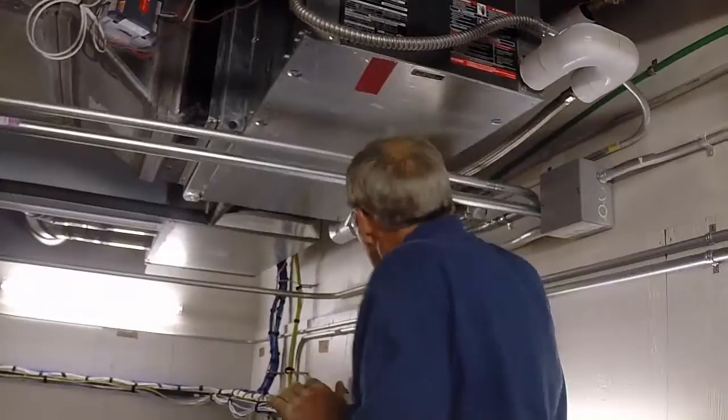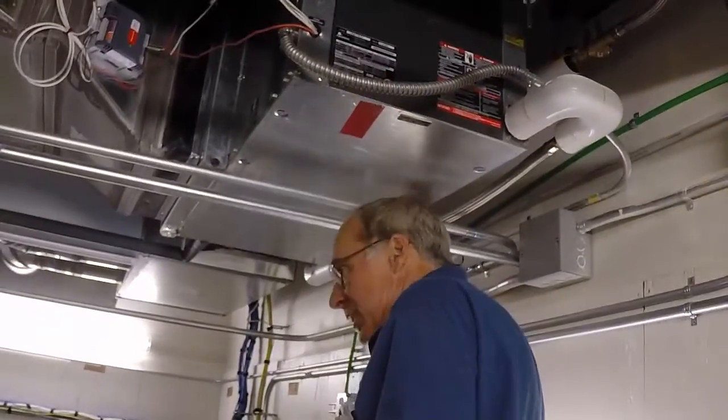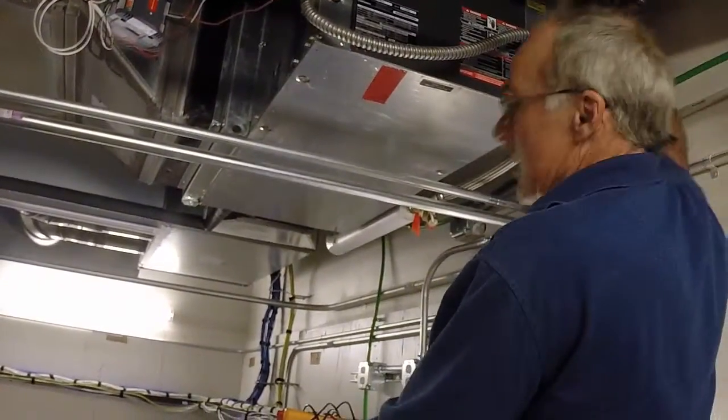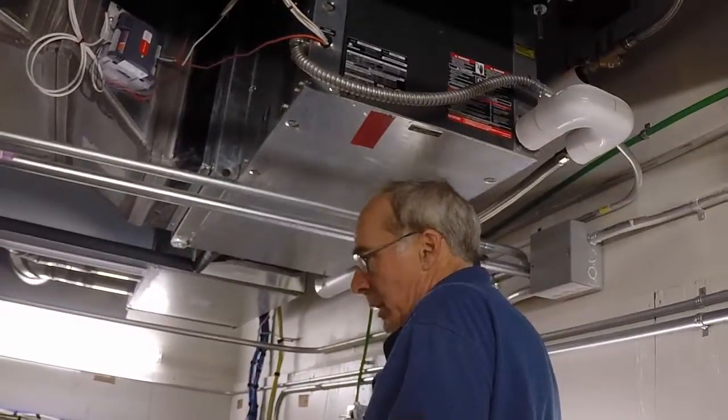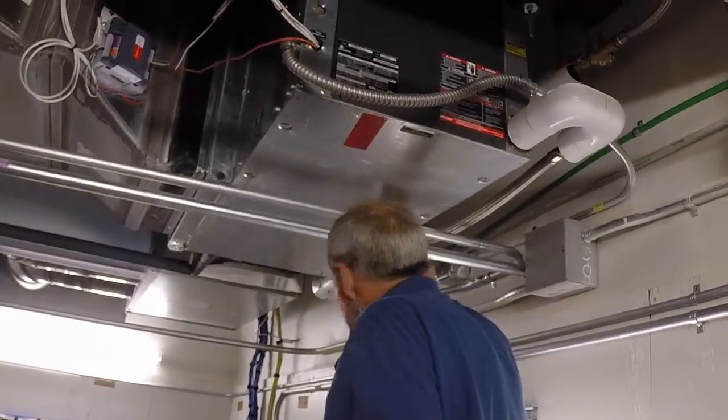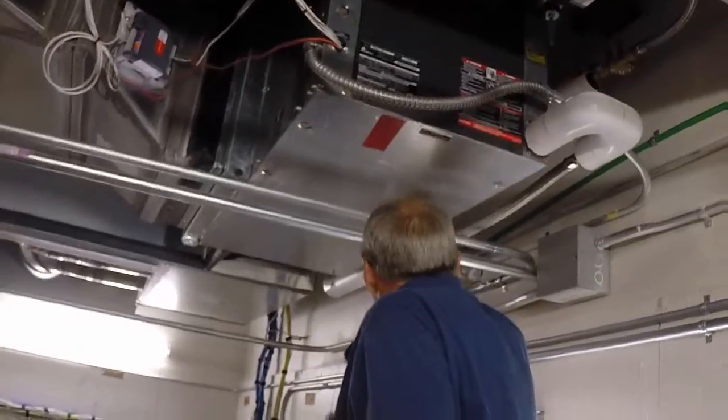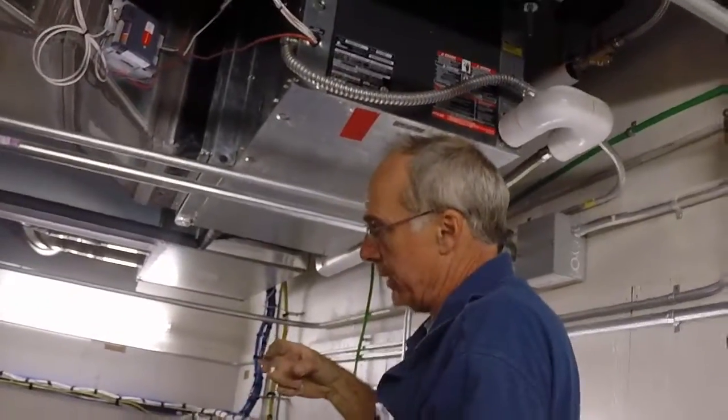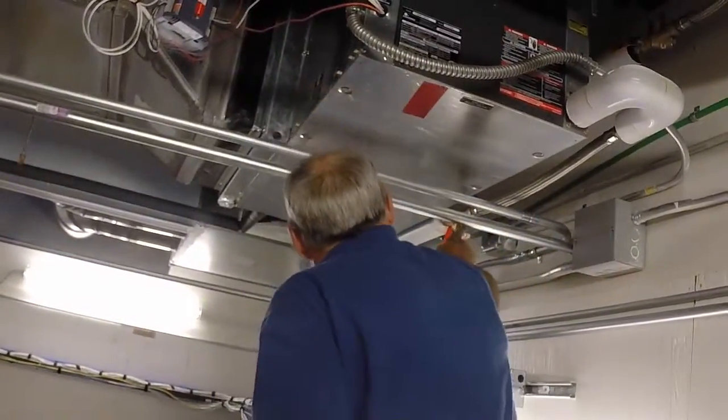The first thing you would look at is if the building pumps are operating. If it's global across the building, then you know it's the boiler room. If it's just one pump, first make sure this actuator valve is wide open. Then I would shut off and check the strainer. There's a hand valve here, and then there's a hand valve on this auto flow valve. Shut them both off, unscrew this cap, get a hose in a bucket, open that up and drain off a little bit. Then you take a wrench right here, and that unscrews. There's an O-ring gasket you can reuse.